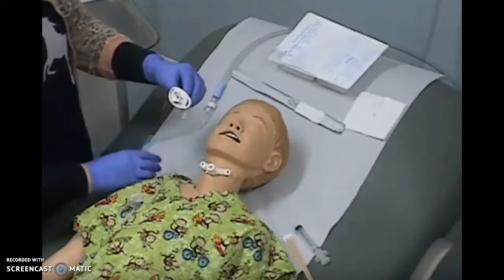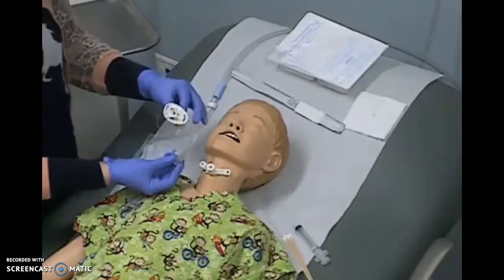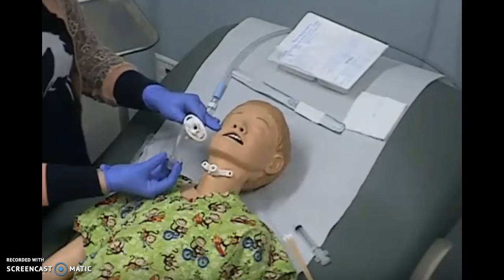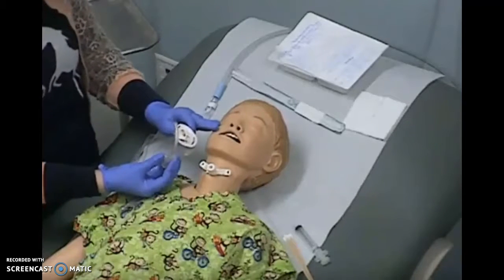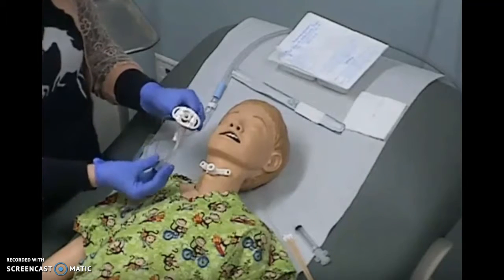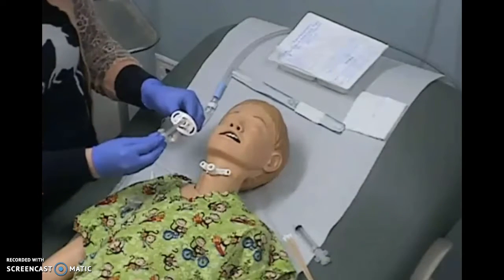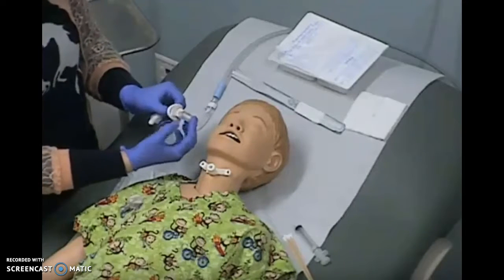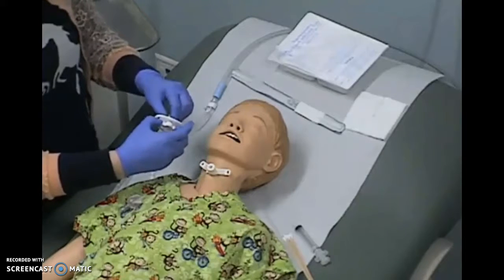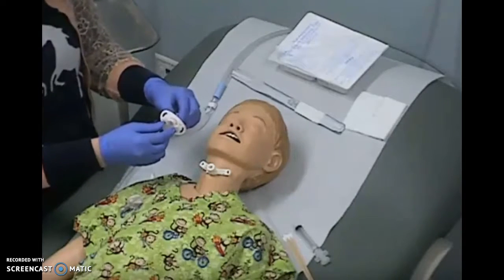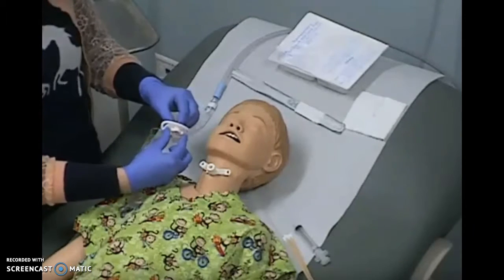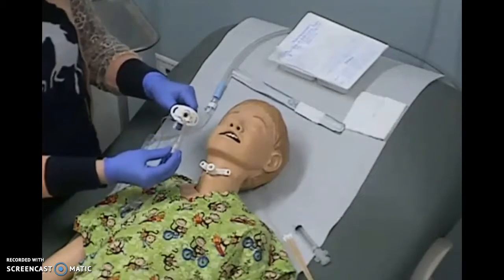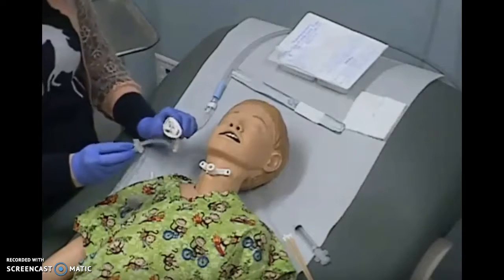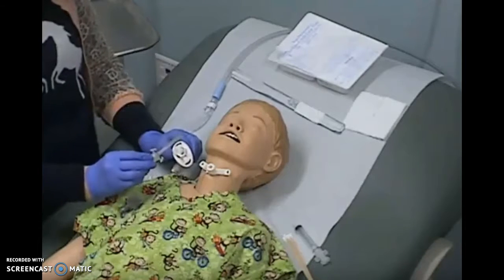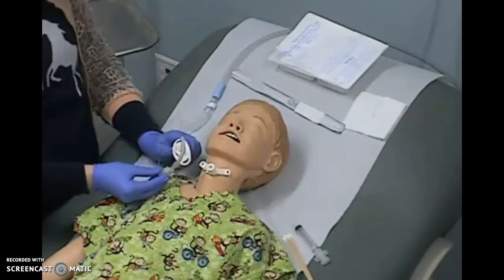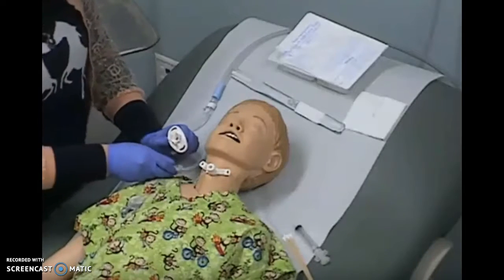Within the actual trach we have an inner cannula that is frequently changed to allow for keeping the airway clean, prevent any type of secretion buildup, and how it works is you find the appropriate size, it sticks in the trach, and then there are flanges that you pinch to lock the inner cannula into place, like so. This then you squeeze out to remove, and depending on the trach available, it is either cleaned with sterile water until it's clean, or else thrown away and replaced with a brand new one.